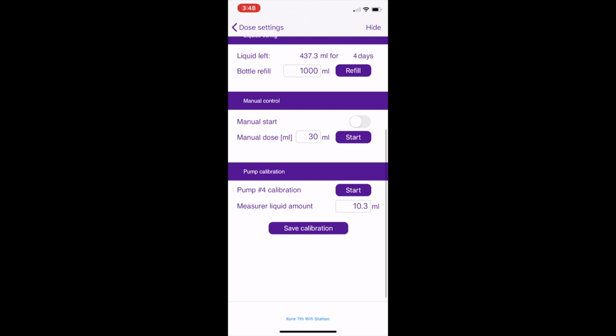You have controls here to be able to manually start and stop the pumps, which can be useful, and you also have the ability to calibrate the pump down here. You simply put the output of the dosing line for that pump into a vial, press the start calibration button, and then you enter the amount of liquid that it actually pumps into that vial as the measured liquid amount. It should be right around 10 ml.